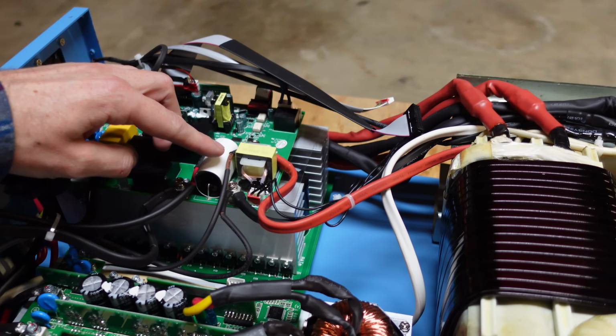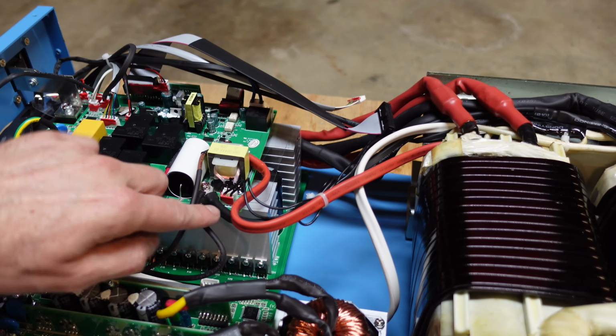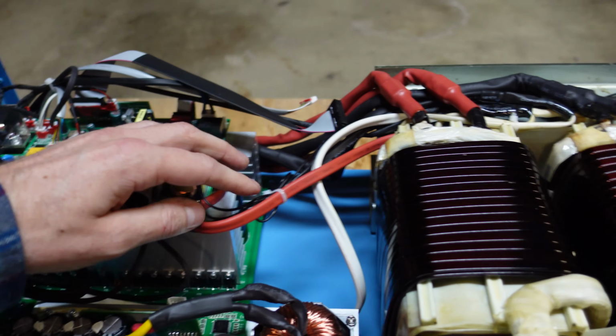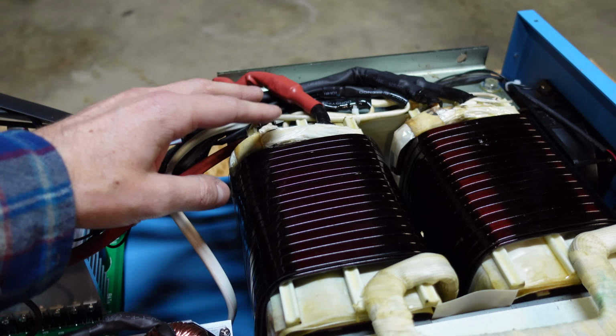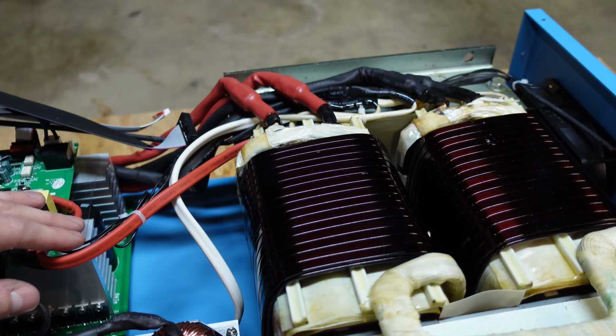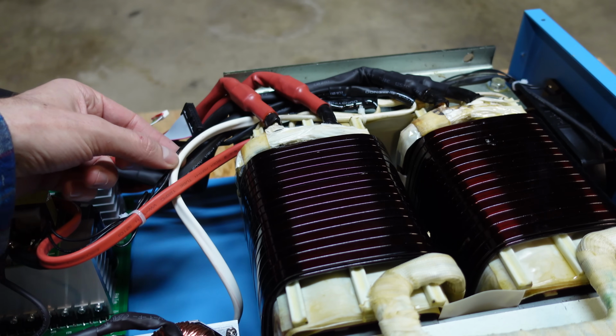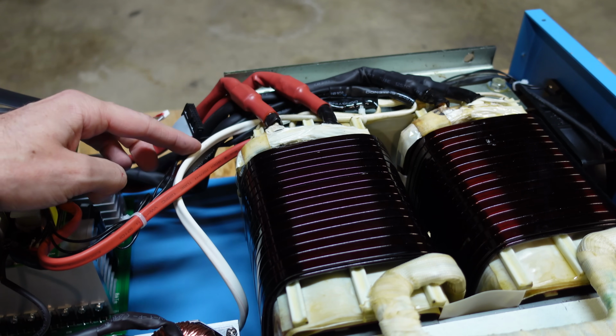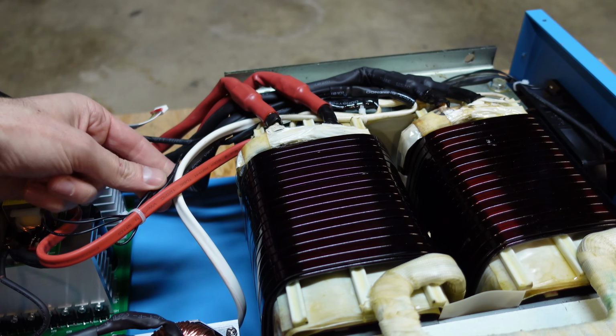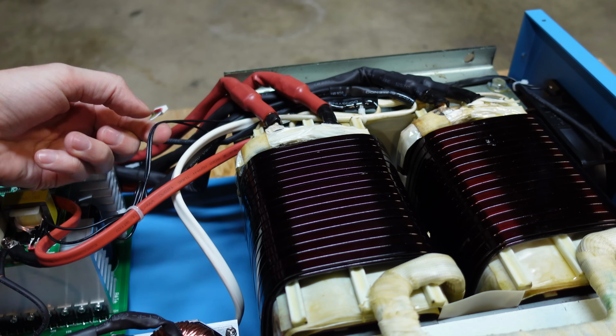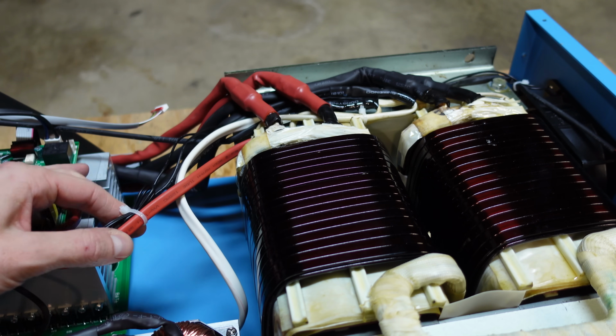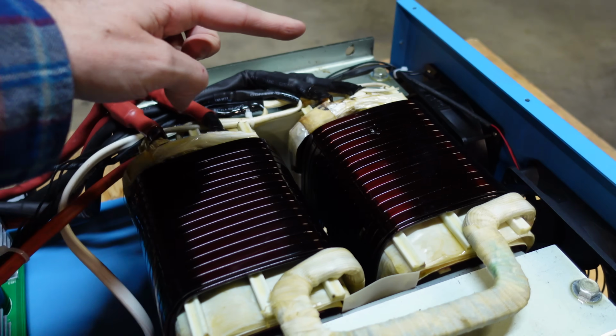Following the AC wiring over, we can see the red and the black are the leg 1 and leg 2. Those conductors come off of the transformer, and that's going to be our 240 volts. Additionally, we have a white line here. This is going to be our center tapped neutral. Additionally, we have a very thin 2-conductor wire here, which is just running from the circuit board. It's tie wrapped on here, and it goes over to the fan on the side of the enclosure.